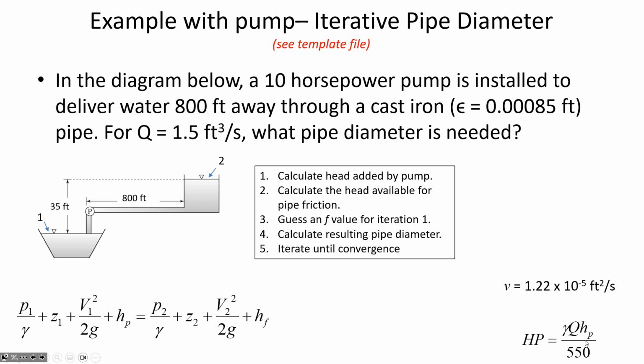And 550 is the number of foot-pounds per second per horsepower. That's the definition of a horsepower, 550 foot-pounds per second.